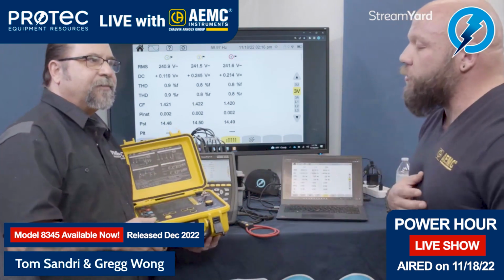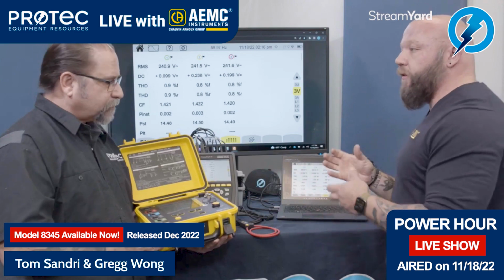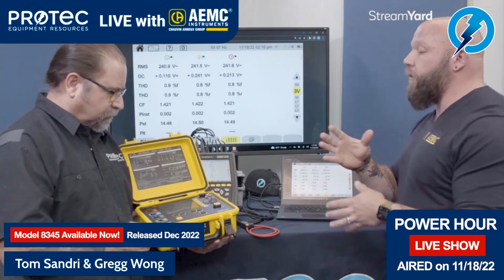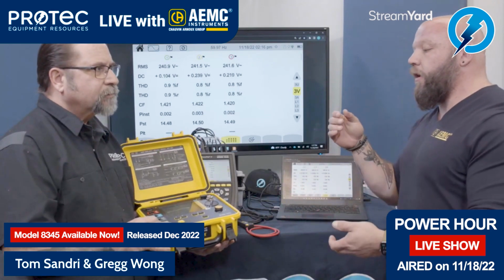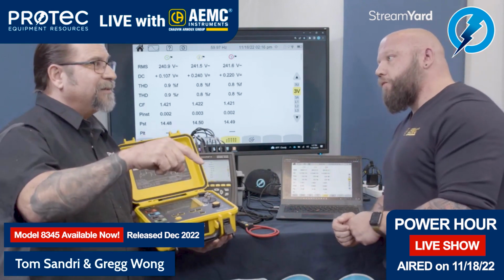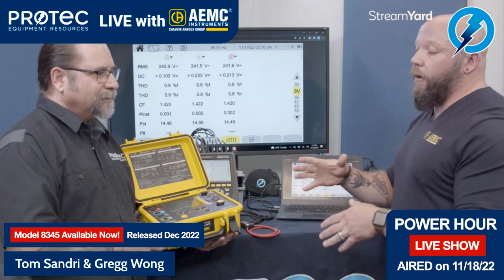That's right. So this instrument is part of that collection of instruments. That's the 6474 tower test or Groundflex Field Kit. It encompasses the 6474, which is a set of high gain amplifiers, with our 6472 ground resistance tester, which is this instrument right here. First off, this is a multi-function ground test instrument, so I can do everything from soil resistivity, fall of potential 3 and 4 pole, step and touch potential for the utility customers out there, and I do have a clamp method that I can use with this as well. Oh, okay. So the attached rod clamp-on method. That's right. Yes. So I can plug 2 clamps into this and be able to perform a clamp-on ground resistance test without having to install stakes.